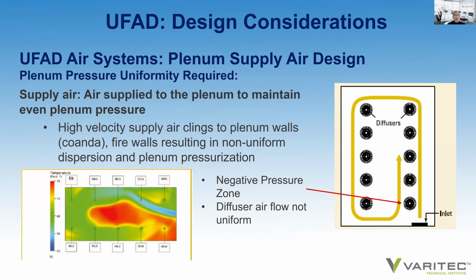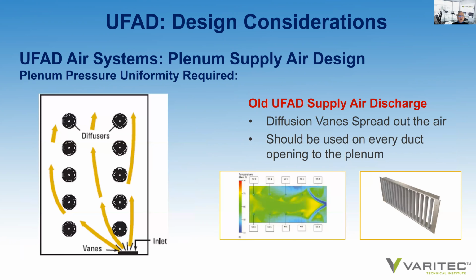Supply air in these designs traditionally, and in the early days, was injected on the interior zones of the UFAD plenum. It was injected at a high enough velocity to project the air across the plenum space. However, in these designs, one has to be very careful that such an injection point is not along a wall where the air will achieve Coanda along that wall and create an imbalance in plenum pressure within the space. You have to be very careful of how you adopt this injection strategy.